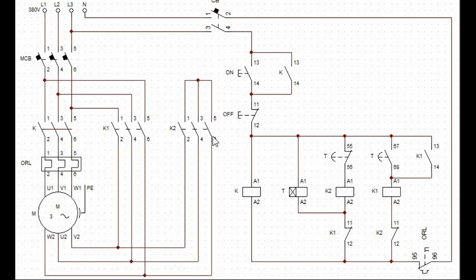Now let's move to contactor K2. The input of contactor K2 is interjumped to create a star connection, and the output of K2 is linked with K1 to create a delta connection.